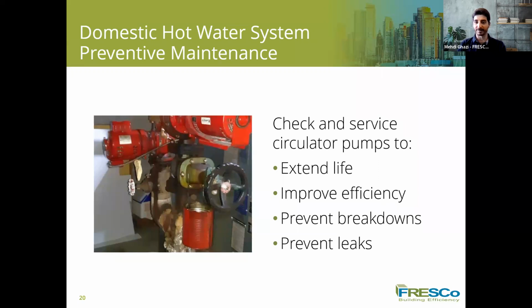We can check our pumps, and we can check for leaks in the flanges and in the pumps. We can touch them, listen to them, and look for leaks, and determine if the motors are running in good condition or have vibration. If there's noise in the motor, that could be a sign of bad performance. So we can have a qualified service contractor tune up our system, so we can prevent failures when we pay attention to any small amount of noise or leak. The benefit of this is a longer equipment lifetime, as well as maintained pumps and motors. They likely last for more than 20 years, while poor maintenance can decrease their life to less than half.